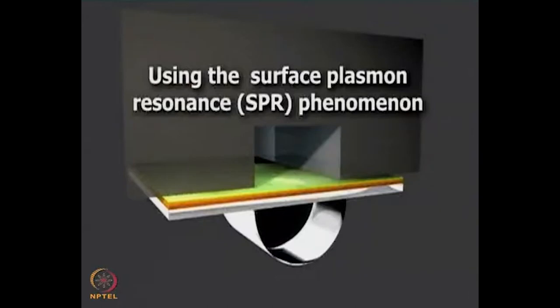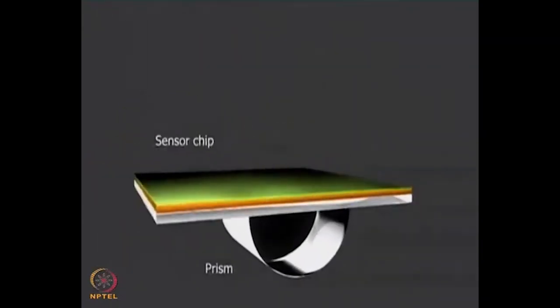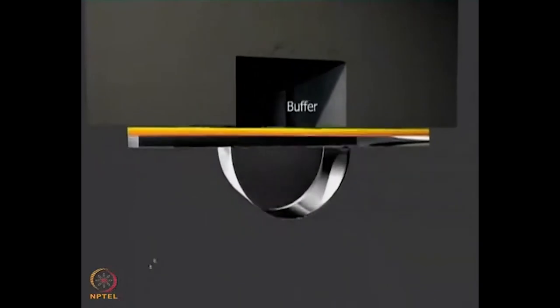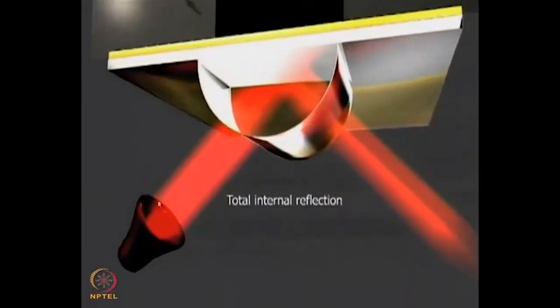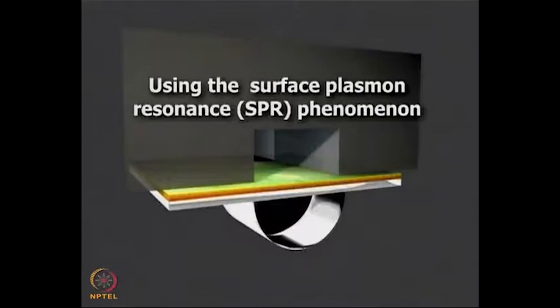What I show here is the basic SPR phenomenon. This is the SPR chip which you see here. On the top of the SPR chip is a gold layer, and on the top of it is a flow cell. At the bottom you see a hemispherical prism. When you actually have the prism and you shine a laser light through the prism, the light reflects at the angle of total internal reflection. Evanescent energy waves are created on the top of the chip, and these evanescent energy waves are also called surface plasmons. These surface plasmons are the ones which are used to actually study biological interactions.